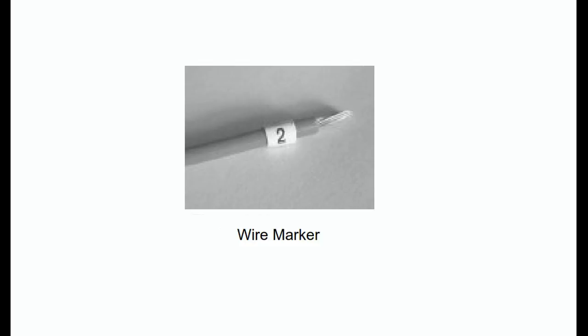Generally, control circuits are wired with all black, red, or white wire. Do not use green; it is reserved for safety ground wiring. Notice that in figure the wire connecting T1 to F1 is not numbered. This is because in our design we will be using a transformer with the fuse block included. Therefore, this will be a permanent metal strap on the transformer and will not be a wire.